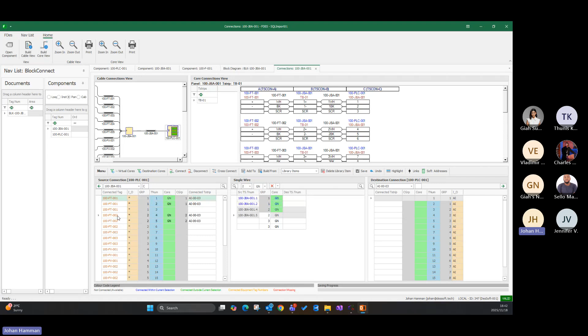So to do the cross wiring within my PLC panel, I just click on the panel itself. It goes into single wire mode, and the source is this T-strip, and then the destination must be my first analog input card. And if I want to use 2 wires to connect to my instrument, then I can say, okay, let's do all my analog ins as green. I've got 3 instruments there, so I add 3 of these groups, and I just connect it to that first flow transmitter, to the second one, and then to the third one. And then from here, from top down, and I can say save these connections.